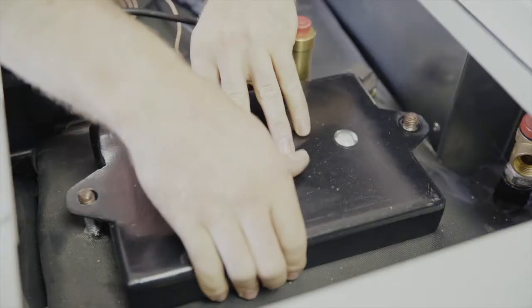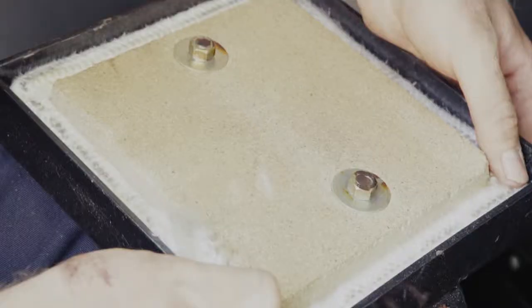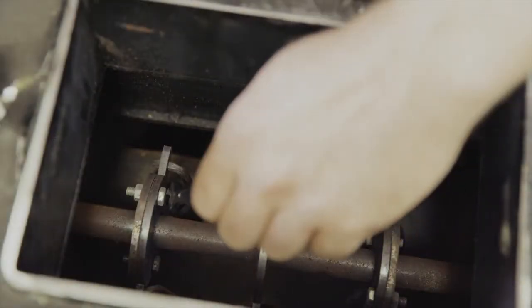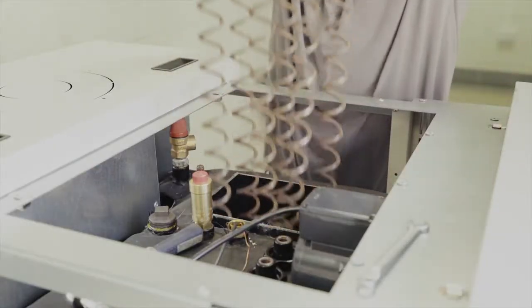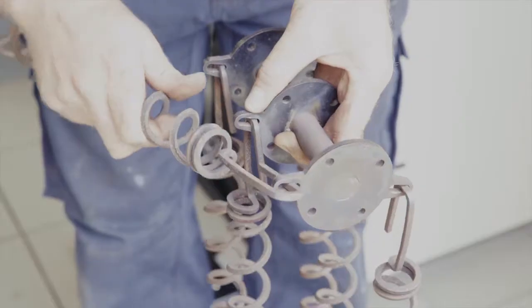When removing the turbulators from the heat exchanger, check if the fiber board needs replacing. Service engineers often neglect to replace this board and it leads to poor quality combustion by air getting sucked in if it's not tightly sealed. Uncouple the crank arm first, then remove the bolts from before and after the pivot plates, and then withdraw the turbulators from the tubes.